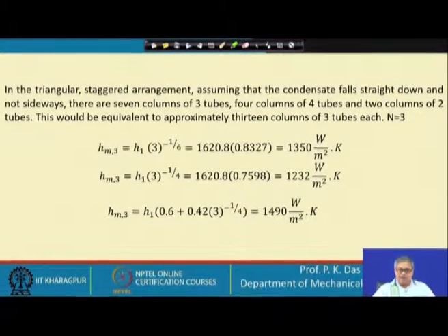In many places in practice we will see that staggered layout of tubes is preferred compared to the inline layout. One reason we can see here is condensation, and staggered layout generally gives a better heat transfer coefficient in single phase flow also.